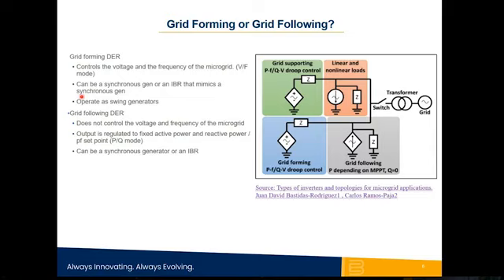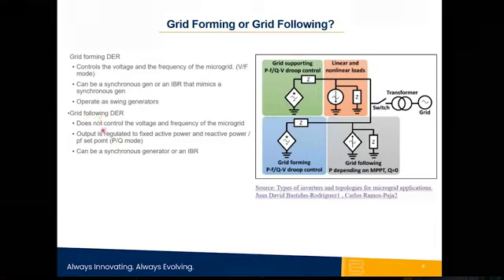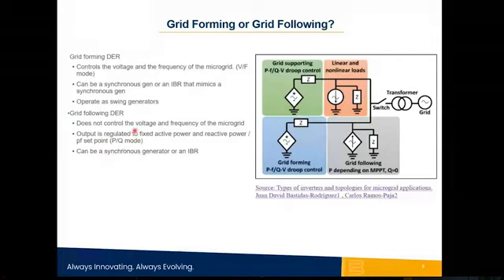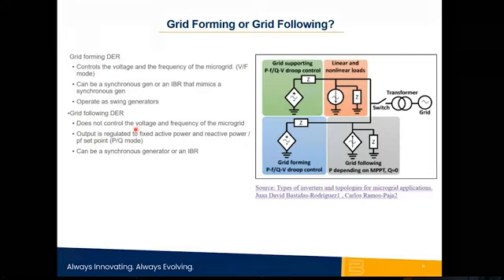A grid following DER works a bit differently. It does not contribute to the voltage and frequency of the microgrid. The grid forming DERs do that. The grid following DERs synchronize to the grid, the bulk grid or the microgrid, depending on whether the microgrid is connected or disconnected from the grid. But regardless of what bus these DERs are synchronizing to, they just synchronize and match the voltage and frequency and they follow. Their output is regulated to a fixed active power and reactive power, or it may be a fixed power factor. But at the end of the day, this is PQ mode, not VF mode, so it's a bit different. They follow the frequency and voltage of whatever bus they synchronize to, and they output a fixed power and VAR or power factor level.